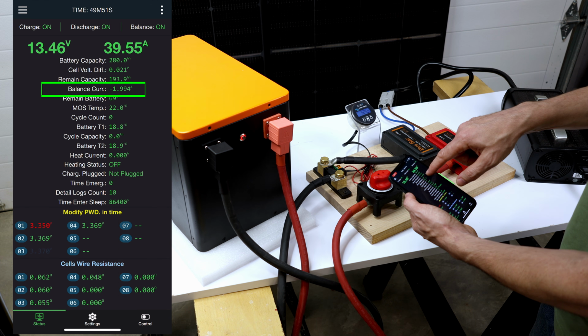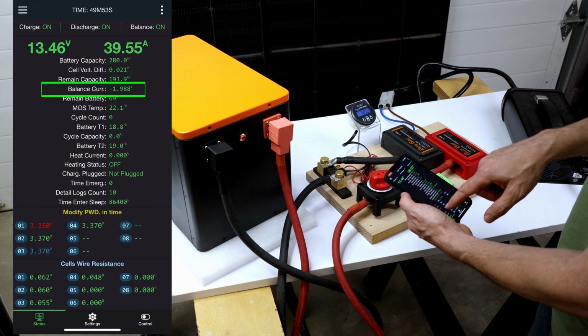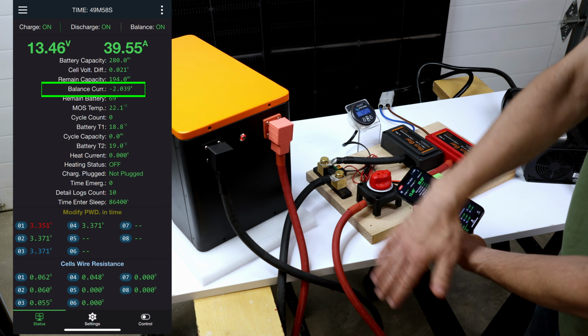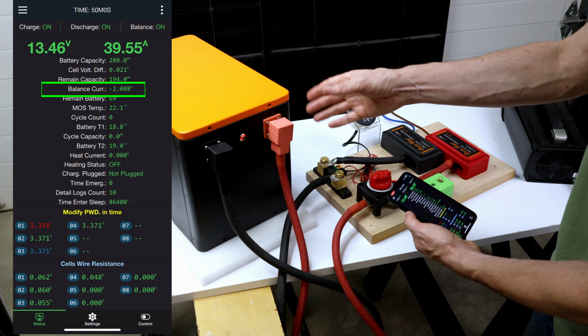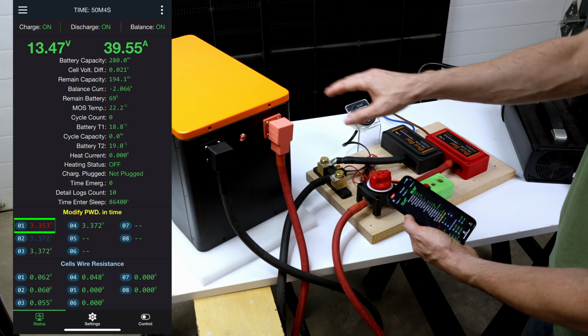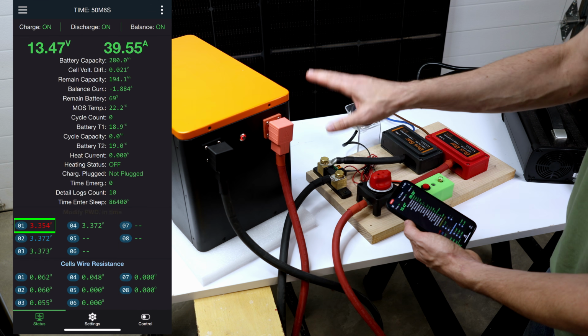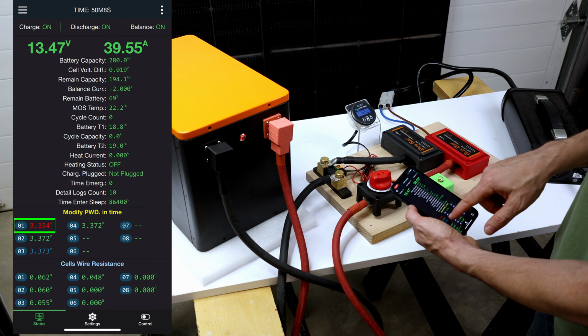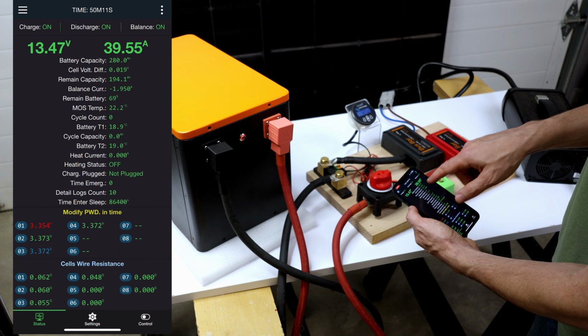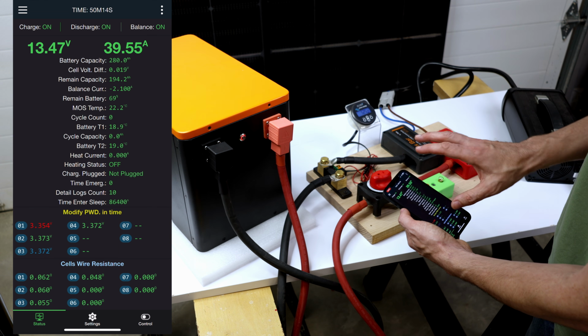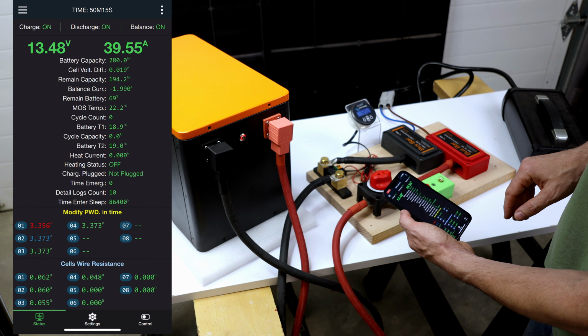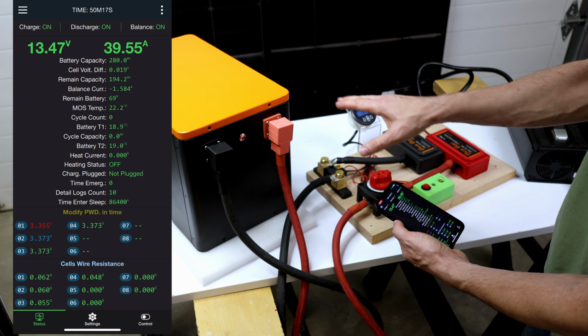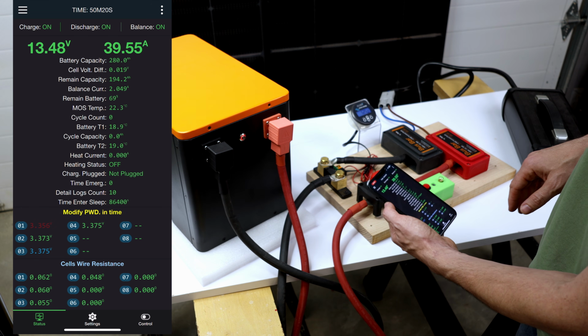You can see the balance current there at 2 amps. One of those cells I completely discharged and then recharged to the same voltage, but the voltage curve is so flat on lithium iron phosphate batteries, that doesn't mean it got charged to the same capacity. We'll probably use that 2 amp balancing current quite a bit to get these balanced out. I'll give it a chance to make sure it's completely balanced before we do our discharge test.